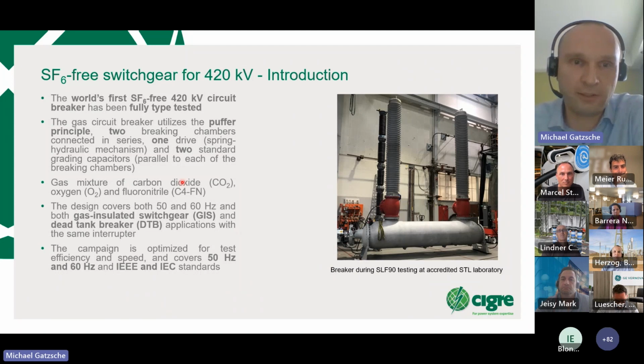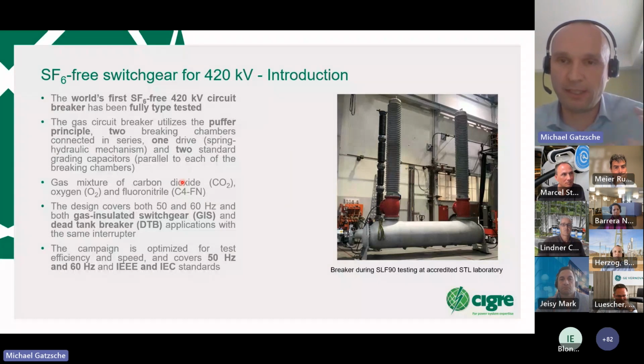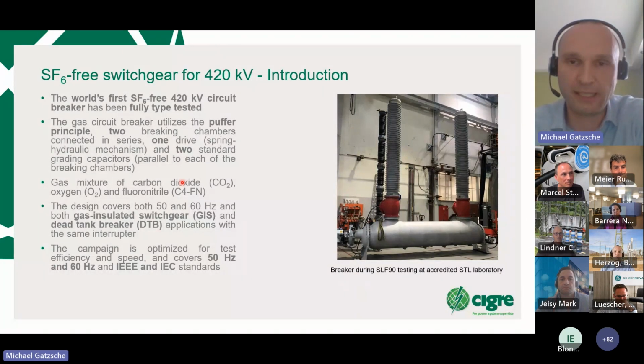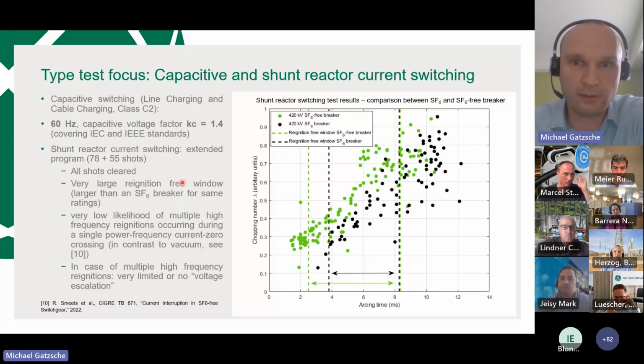The gas circuit breaker uses a gas mixture of carbon dioxide, oxygen, and fluoronitrile. As you will see later on, it is really a platform approach. The same interrupter has two main applications, for GIS and for dead tank breaker. It also covers 50 and 60 Hertz, so IEEE and IEC, and was tested accordingly. I will go a bit more into detail on the next slide.